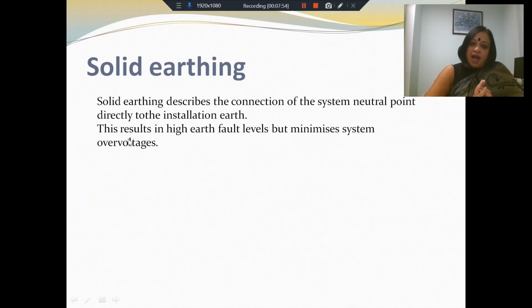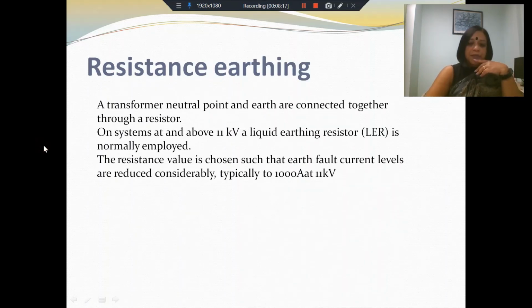So solid earthing describes the connection of the system neutral point directly to the installation earth. This results in high earth fault levels because you're not limiting the fault current in any way. So the current that is flowing from the neutral to the ground is as high as can be under fault conditions, but it does minimize system overvoltages. But we prefer impedance earthing.